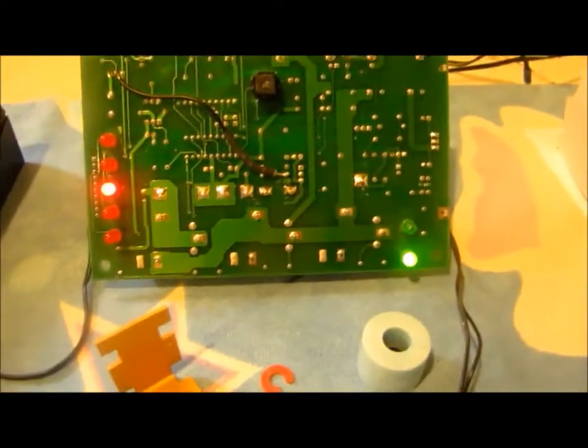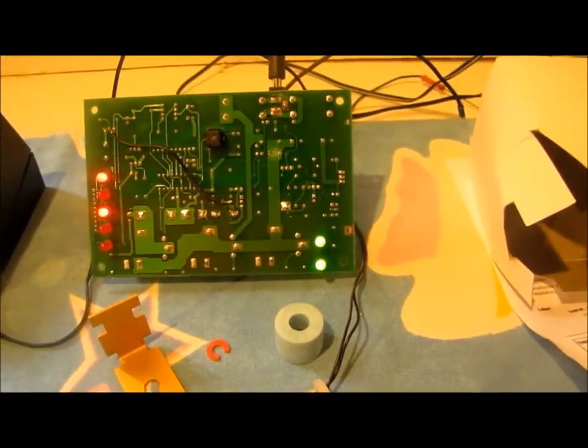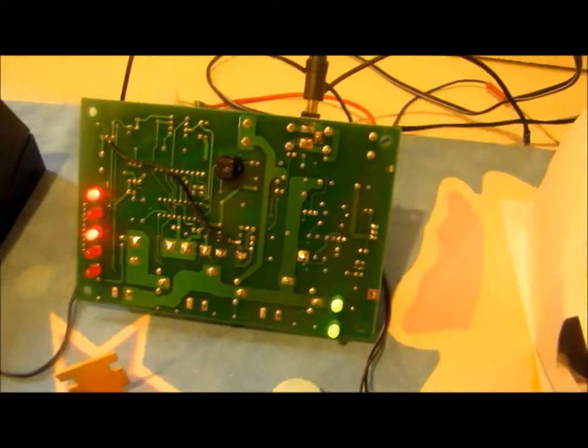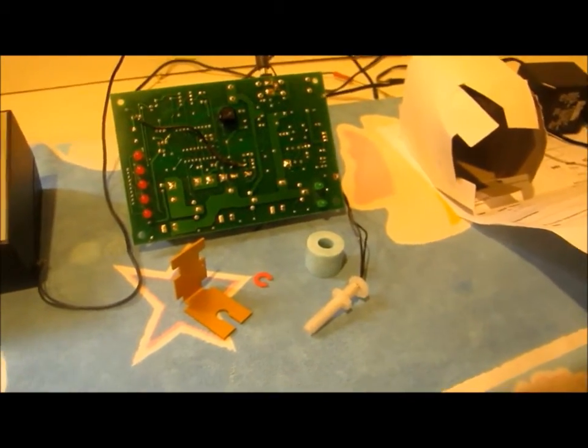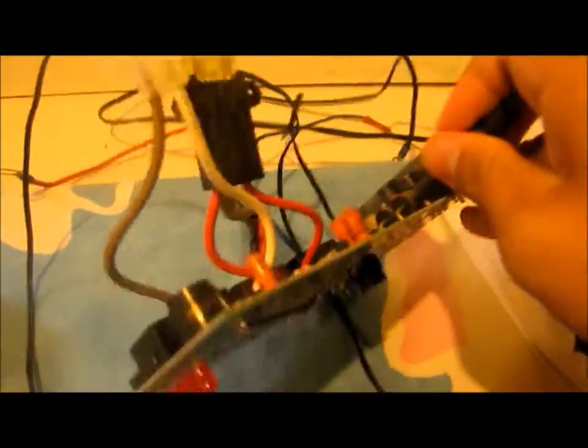It does work — that's the water alarm, and that's the system operating light. I'm showing the battery alert right now, so I'm going to take that off because the noise is bugging me. It does still work. It just comes with false battery alerts because it was not surge protected, so I believe it got damaged by lightning. Let me take the charger out and look at the back side of it.